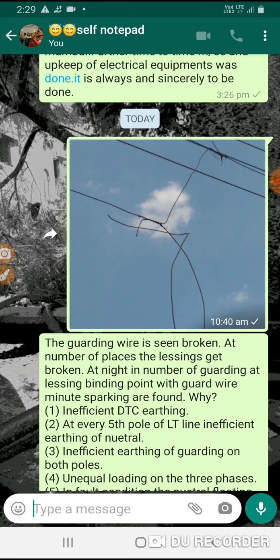And the guarding is essential to rest the conductor, or the broken conductor, to avoid its falling on humans and animals, and to avoid accidents. Hence, I think you have got my point. My point is that the breakages and damages of guard wire or lacing are due to a bad earthing system, improper fuse size, and unequal loading of the three phases of a DTC. This is what I wanted to emphasize to protect the guardings.